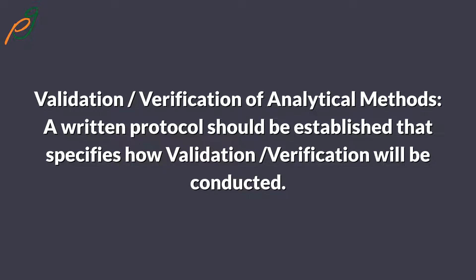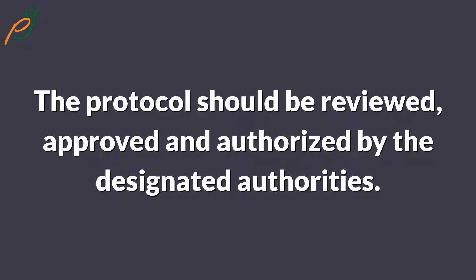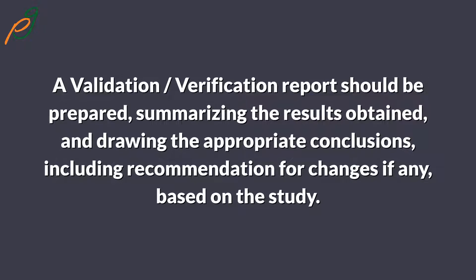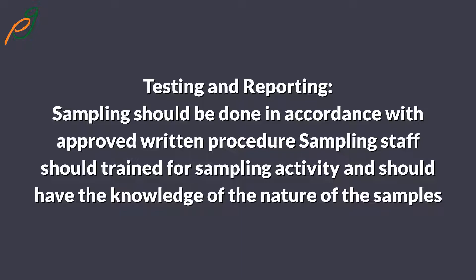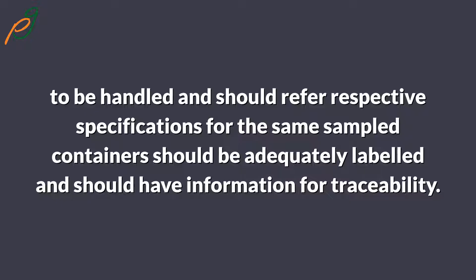For validation and verification of analytical methods, a written protocol should be established specifying how validation and verification will be conducted. The protocol should be reviewed, approved, and authorized by the designated authorities. A validation/verification report should be prepared summarizing the results obtained and drawing appropriate conclusions, including recommendations for changes if any. Sampling should be done in accordance with approved written procedures, sampling staff should be trained, and sampled containers should be adequately labeled with information for traceability.